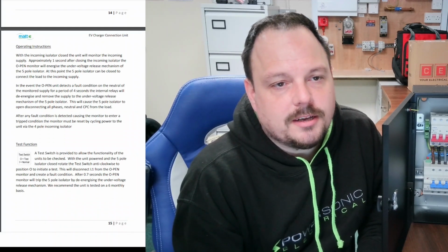So the incoming isolator closed. The unit will monitor the incoming supply approximately 1 second after closing the incoming isolator. The open monitor will energize the under voltage release mechanism of the five pole isolator. At this point, the five pole isolator can be closed to connect the load to the incoming supply.